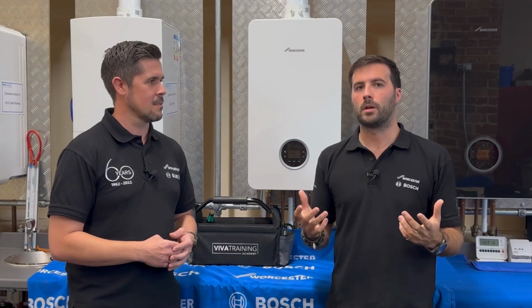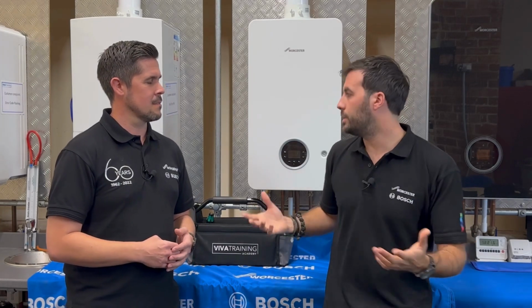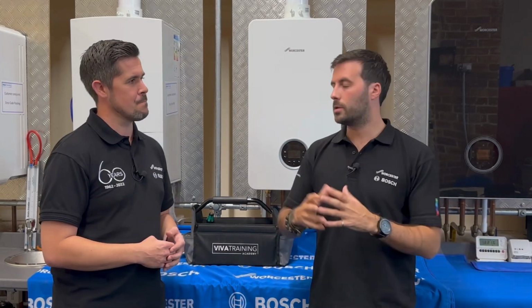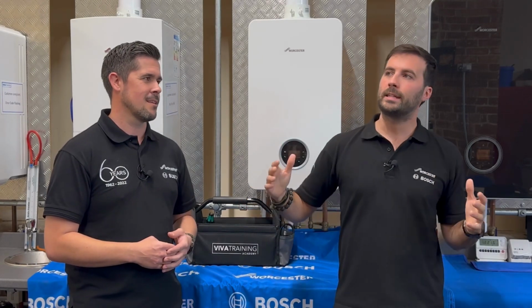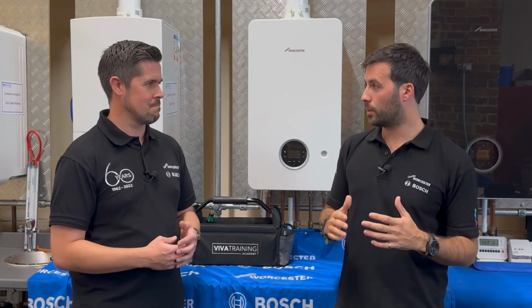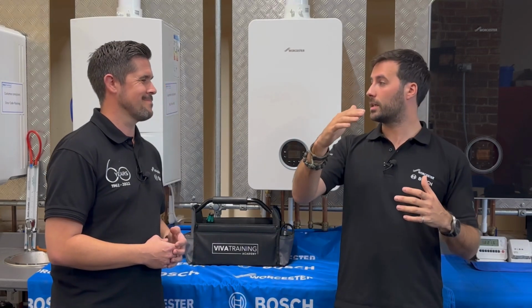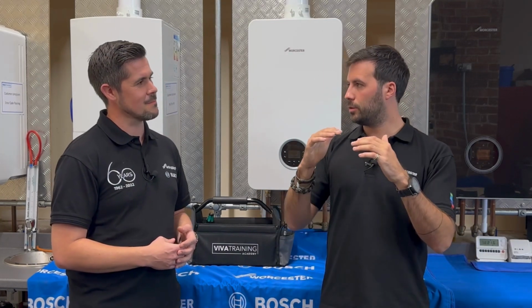So when you look at a gas boiler, we say they're 92% efficient. You buy it off the box, 92%. If you can get that return temperature down as low as like 35 degrees, your efficiency goes up to like 96% when you look at the guidance from the Domestic Heating Design Guide. So that will always vary, but you can improve your efficiency by having lower flow temperatures.